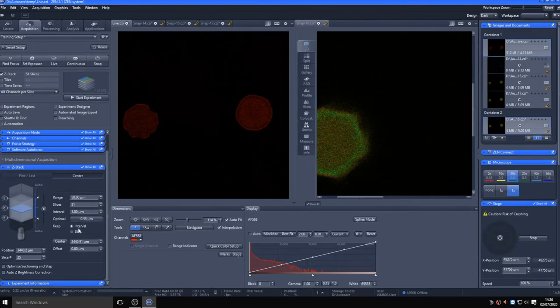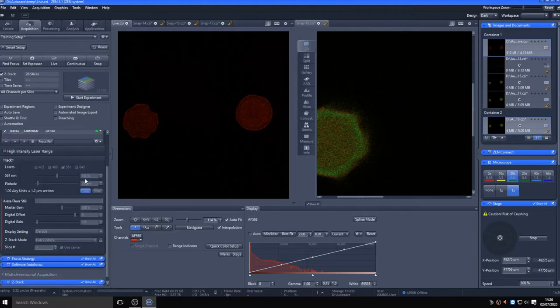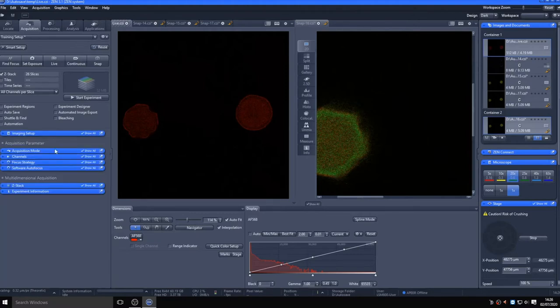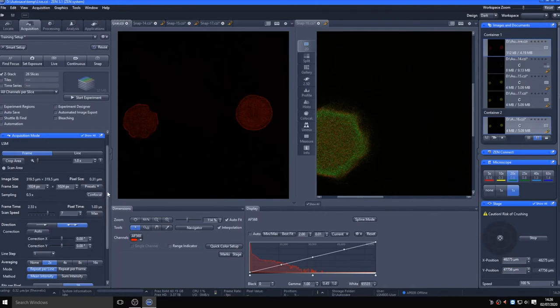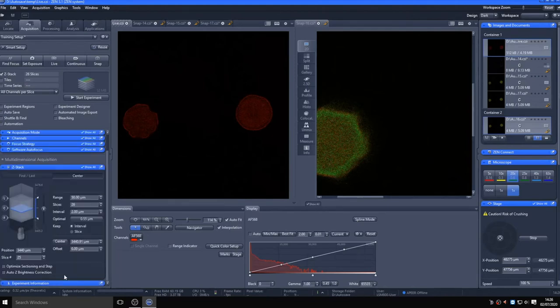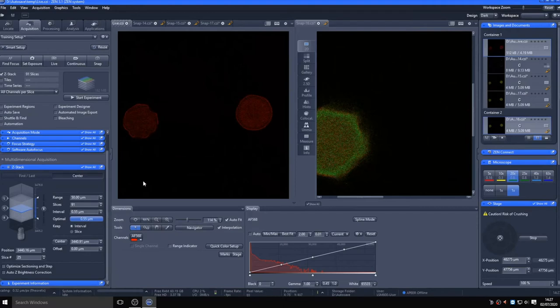In a similar way to the XY acquisition mode, where there is the option of manual frame sizes and a confocal setting where an optimal number of pixels is chosen to gain maximal resolution from the lens as determined by the numerical aperture of the lens, there is an optimal setting for Z sections, which is determined not only by lens NA but also by the diameter of the pinhole. This optimal setting is approximately half the optical section depth as set by the pinhole, such that there is overlap between sections and no data is lost. Be careful when setting the Z interval so that banding is not seen in your final image due to undersampling.